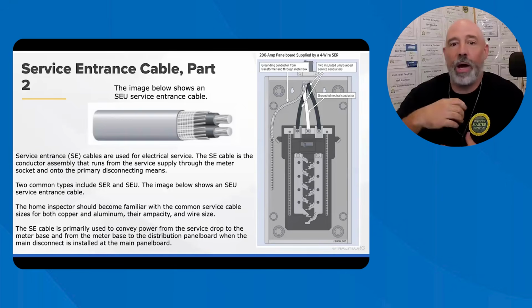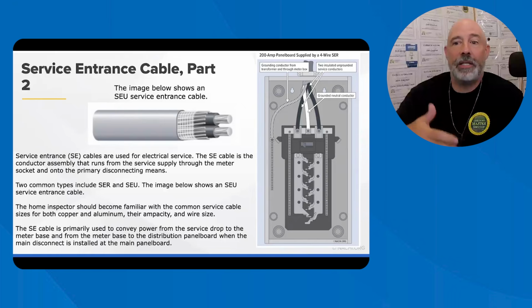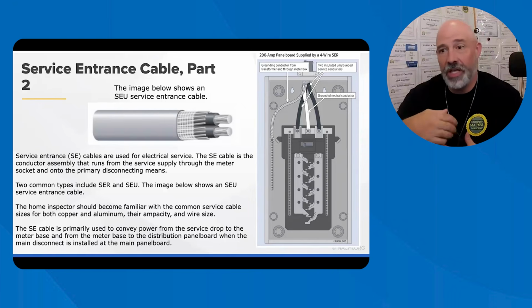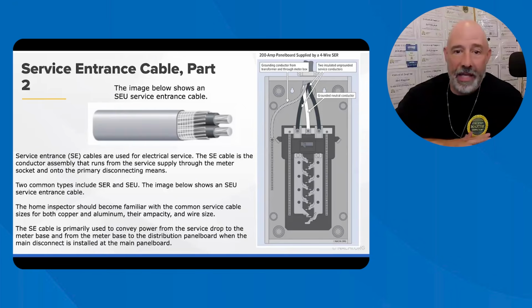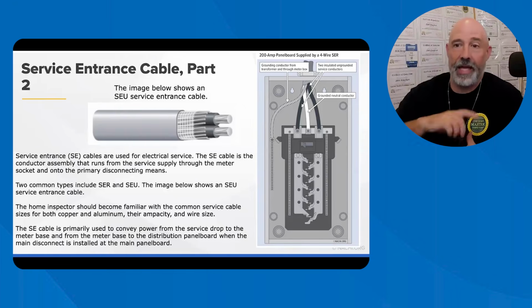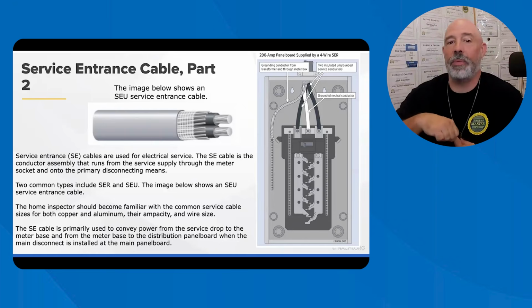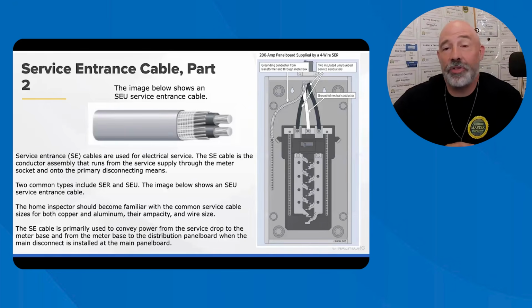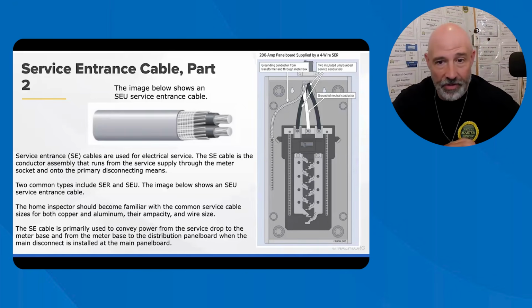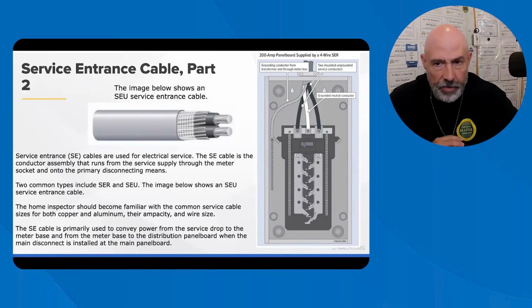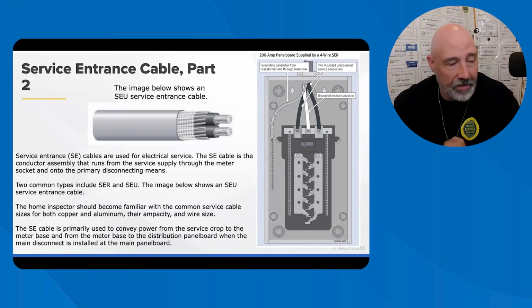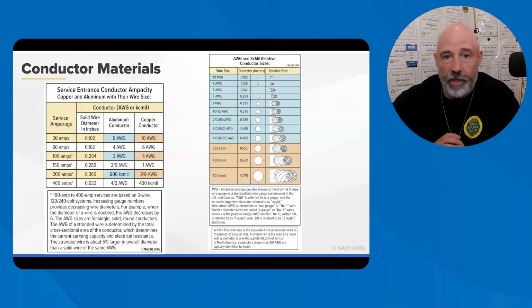The SER is the round service entrance four-wire cable that typically has up to four conductors and a bare neutral. The cable is designed to be used in feeders and branch circuits. The SER cables are equipped with neutral and grounding conductors, which makes them perfect for use after the service disconnect. The image here shows a 200 amp panel board supplied by a four-wire SER, where the main service disconnect is installed at the meter outside and an additional disconnect is installed at the panel board, it looks like. So hopefully everybody understands that.